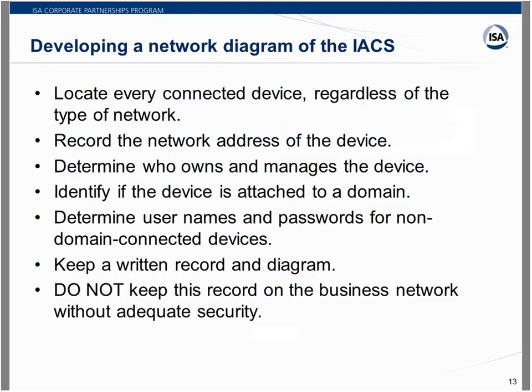Some people, the automation people own it, other people. We go to surveys all the time where we find a firewall or a jump server, remote access server is another word for that, that nobody knows who manages that. And if there's no manager, that probably means it's not getting patched. That probably means it's not getting any updates. It might not have any security applied to it because nobody's claimed ownership. So knowing who owns and manages the device is something that you should record and know for everything connected to that network.